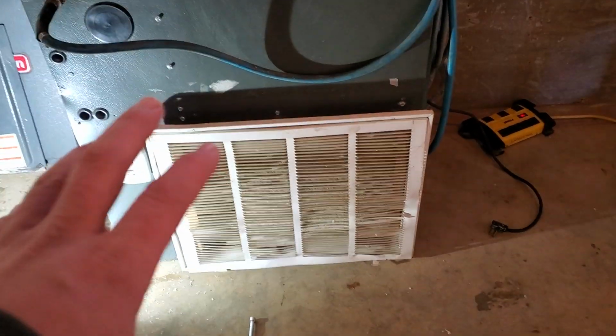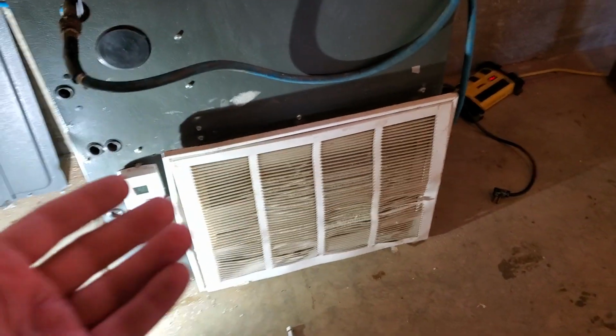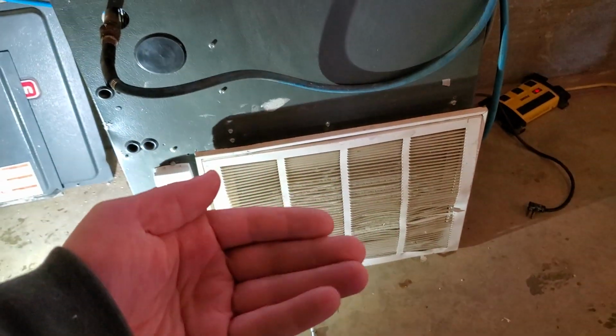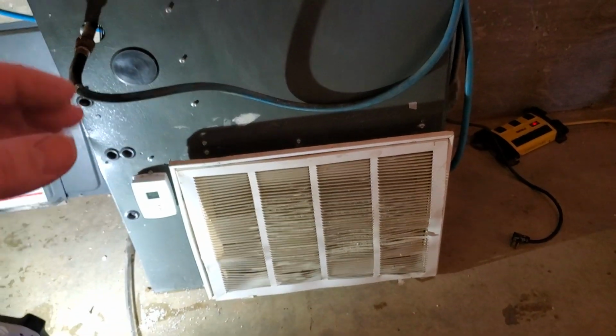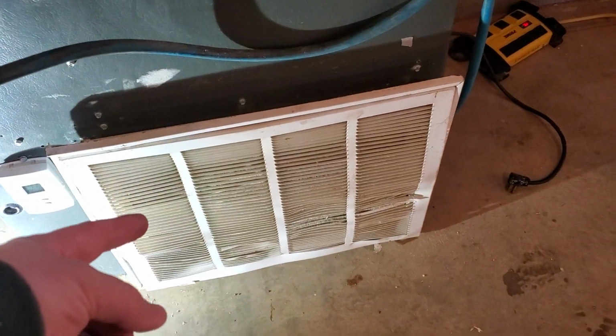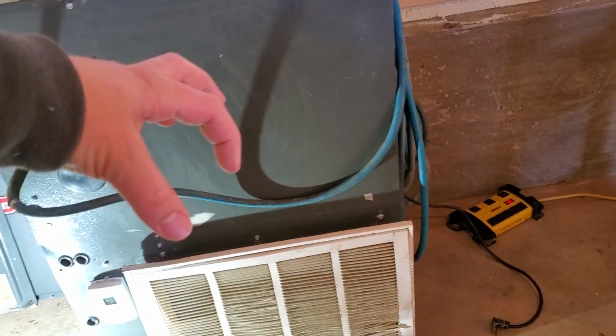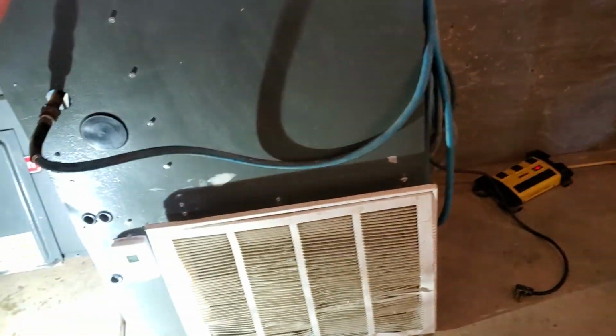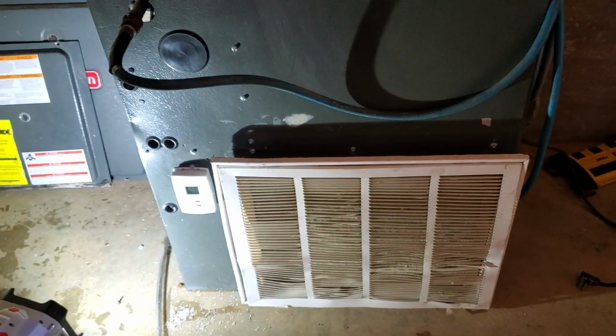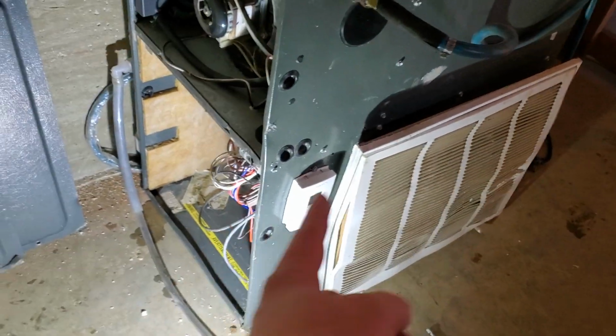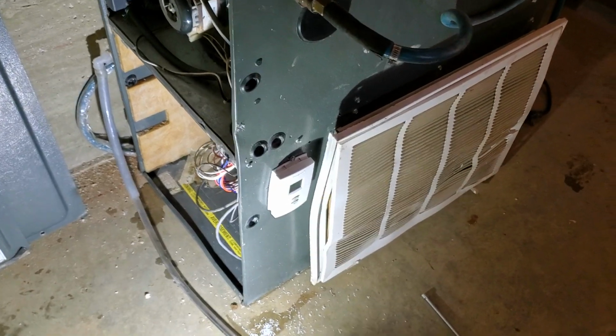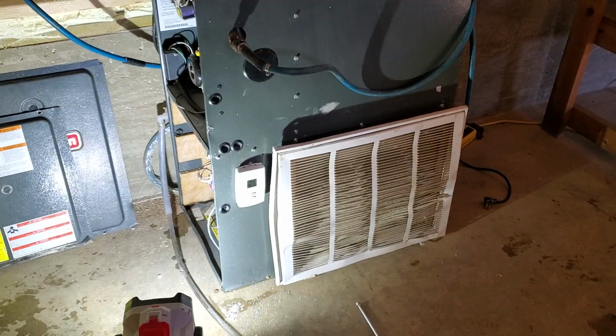The other reason that air filter is really important is that the secondary heat exchanger inside of these furnaces is typically like a coil. And so if you don't have a filter in there, it's going to plug up that secondary heat exchanger, and then your furnace is not going to work until you slide that blower out of there and clean that secondary heat exchanger.